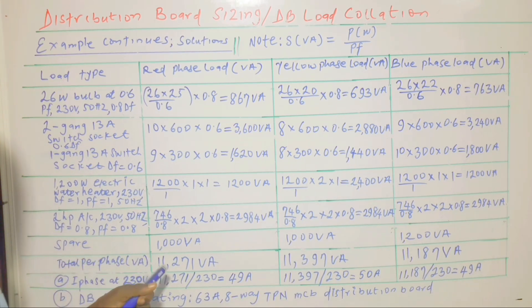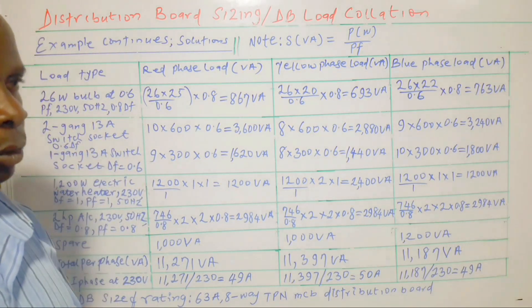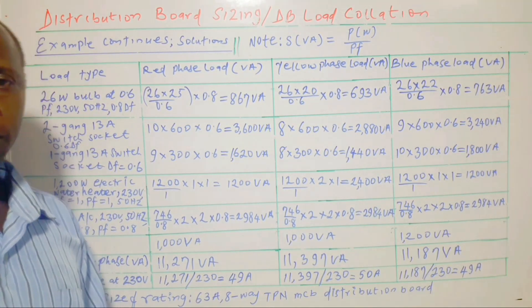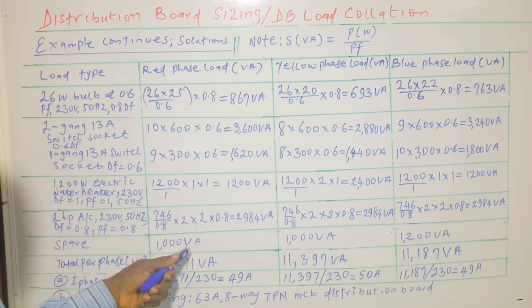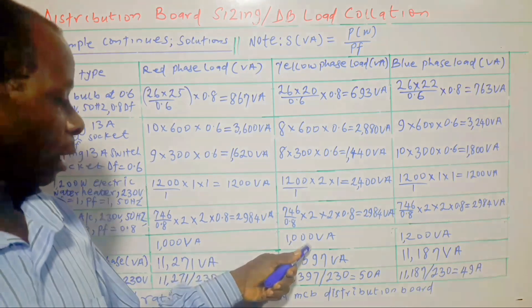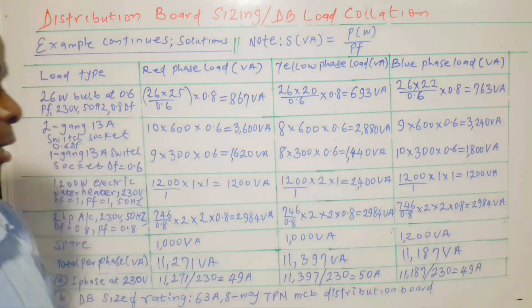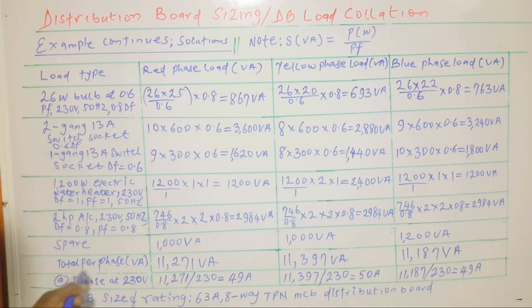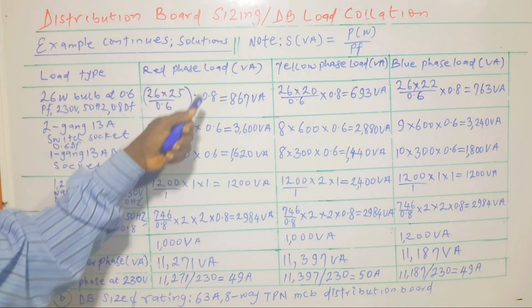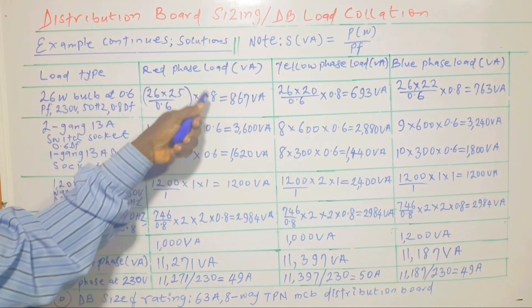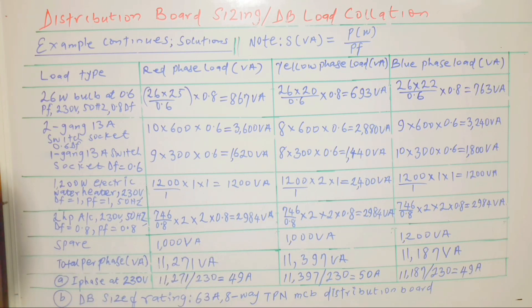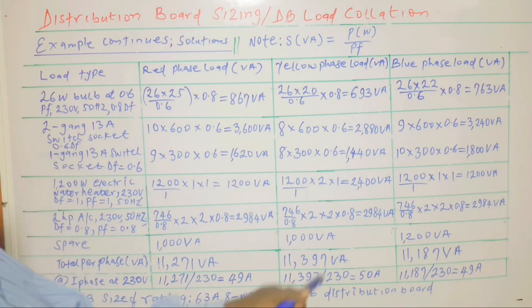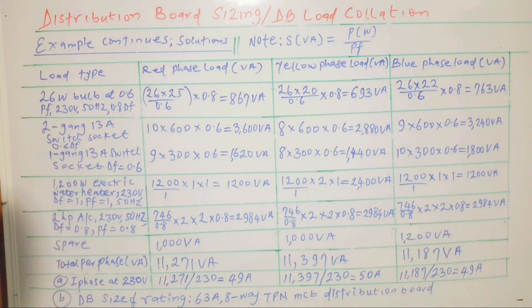We also need to provide spare capacity in case the building user wants to connect additional loads in the future. So we are providing 1,000 VA, 1,000 VA, and 1,200 VA as spare loads for each phase respectively. We then add all the values together to get the total VA per phase. The same summation is done for the yellow phase and the blue phase, giving us our results.